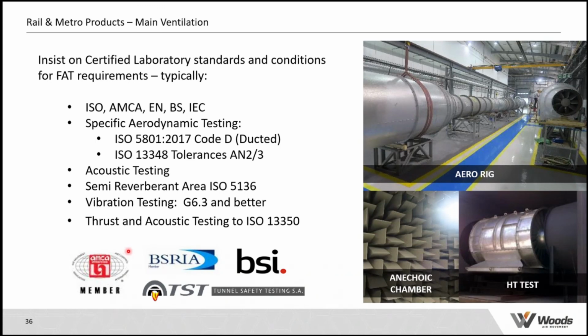So we have a dedicated facility to test the fans. This is just showing the standard test rig. So as you can see, to do an aerodynamic performance, you end up with a lot of ductwork, and particularly when you have a 2.5 meter fan, it becomes an extremely long piece of ductwork. But I think the important thing here is that the fan should be tested.